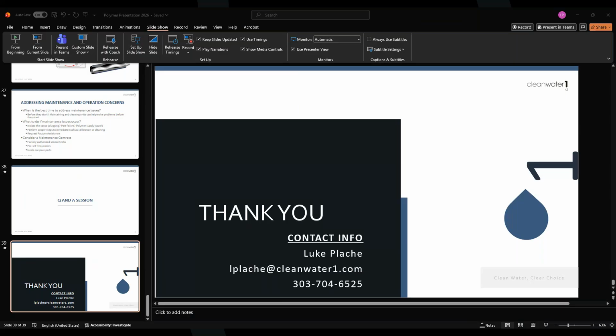What we didn't cover was dry polymer. With dry polymer, you always have to have a mixing aging tank, and you always need to have two tanks. The reason that's really important is that we need to isolate the newly made down polymer from the polymer that's being fed to the process. Dry polymer requires a full batch cycle of being wetted, mixed, and aged before it's fully activated and ready to feed to the process.